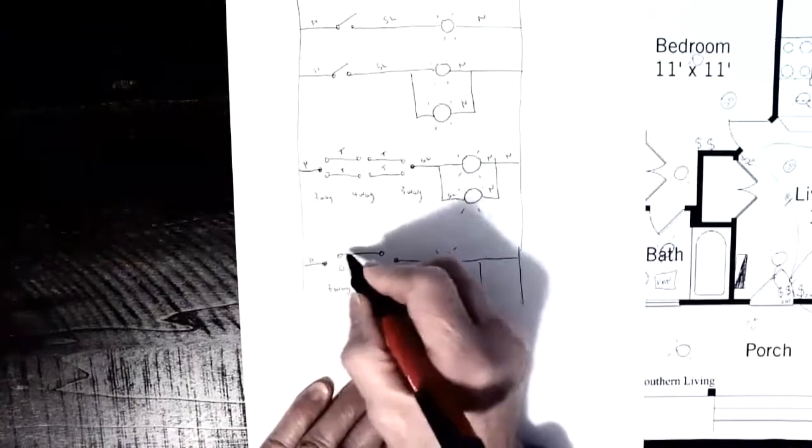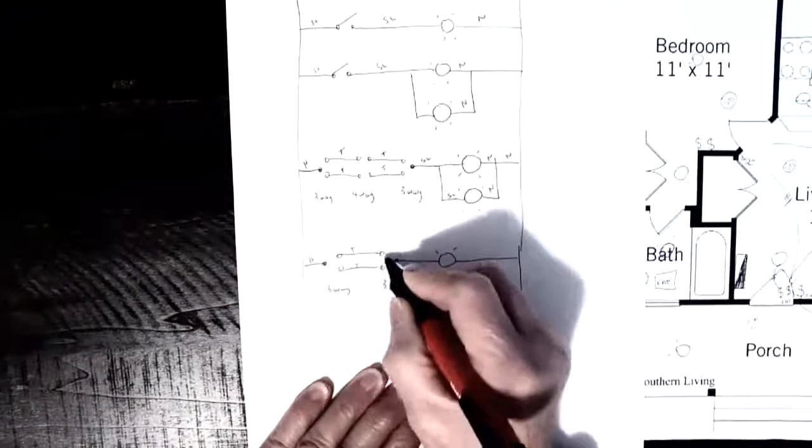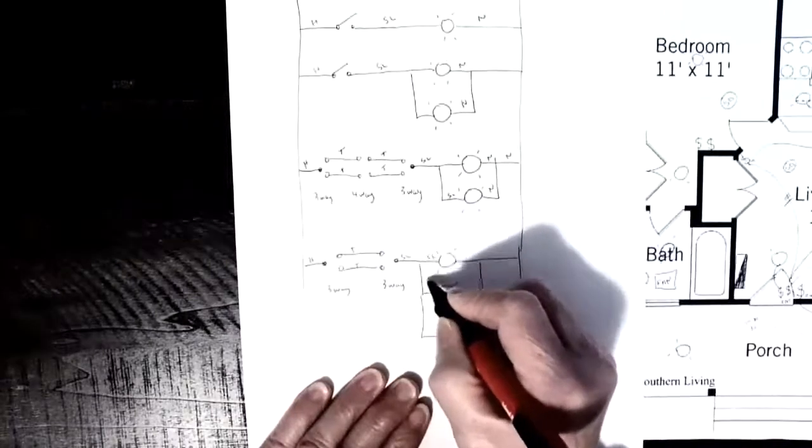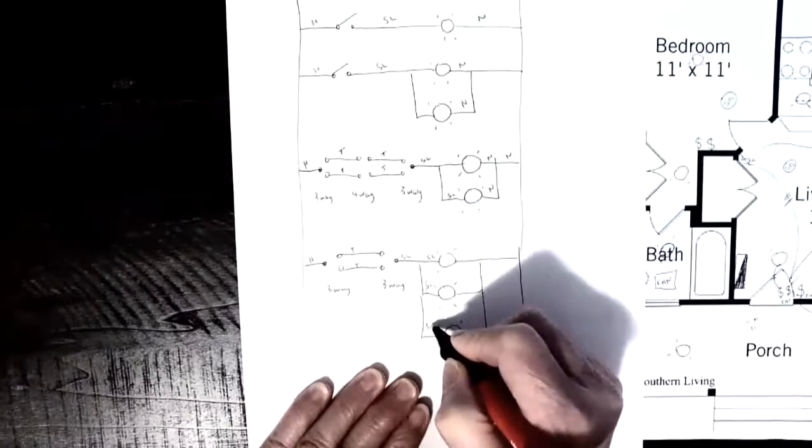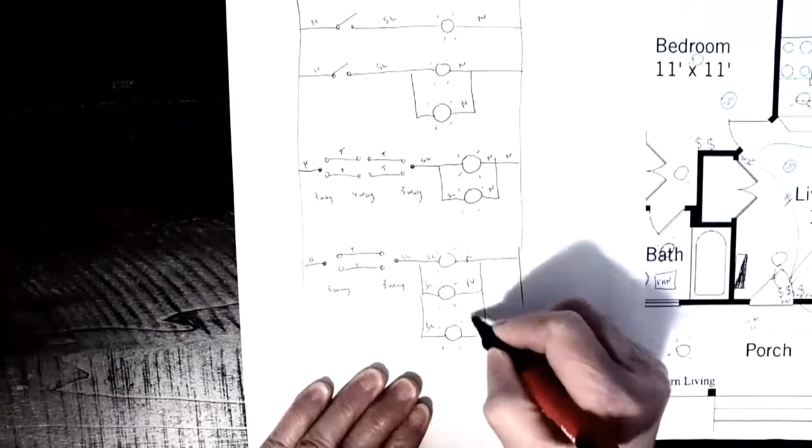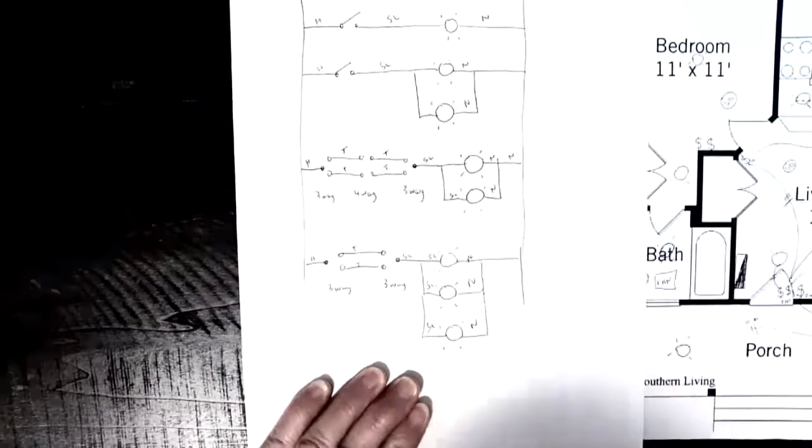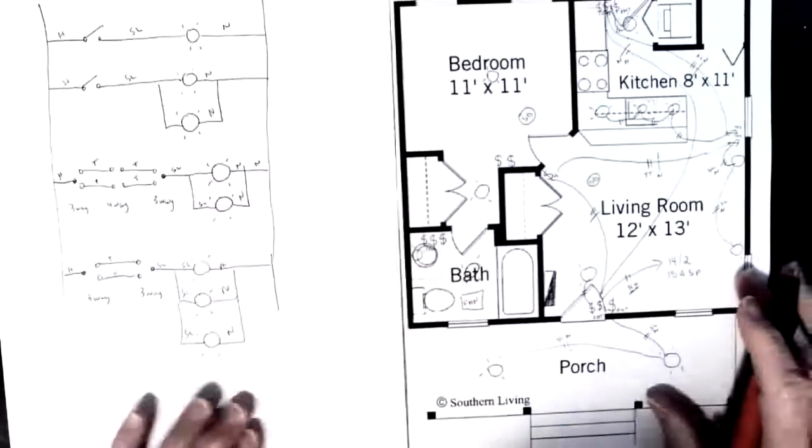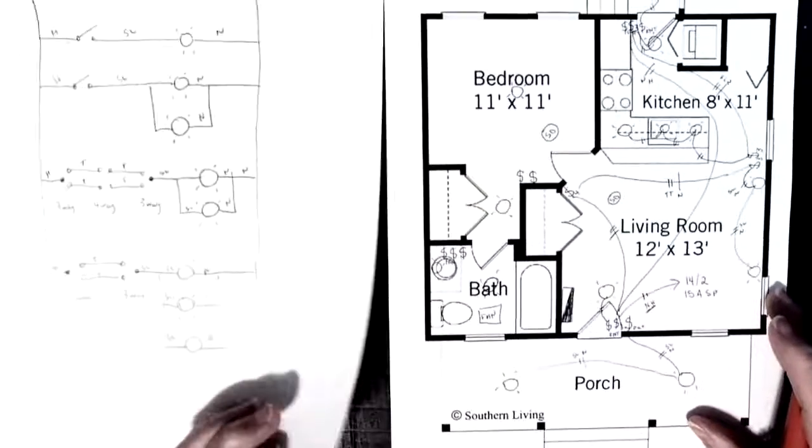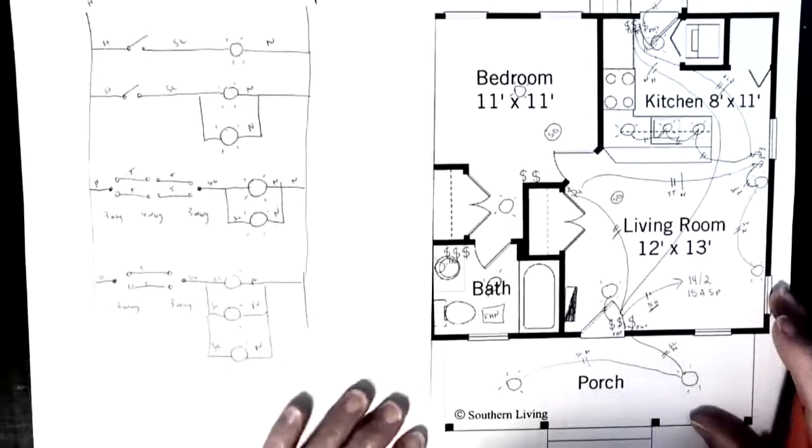So we have a hot going to the common. We have travelers going to the second three-way. We're going to have a switch leg leaving that second common. The switch leg goes to each one of those lights, and then our neutrals head back to the panel.